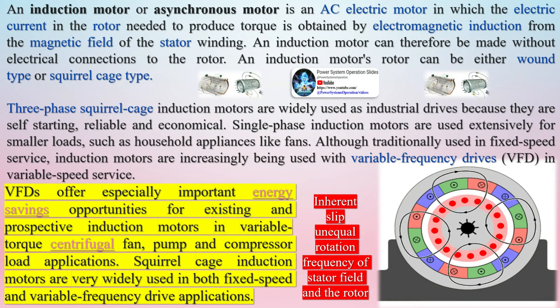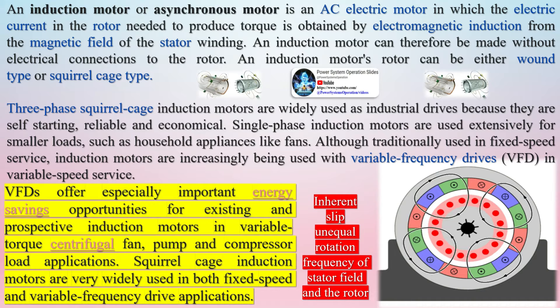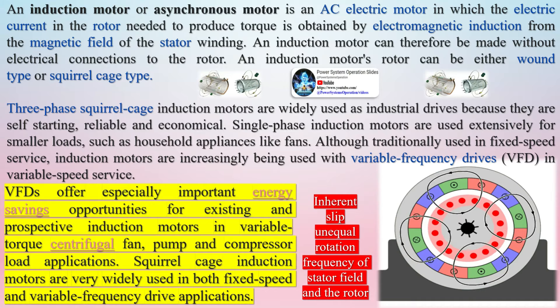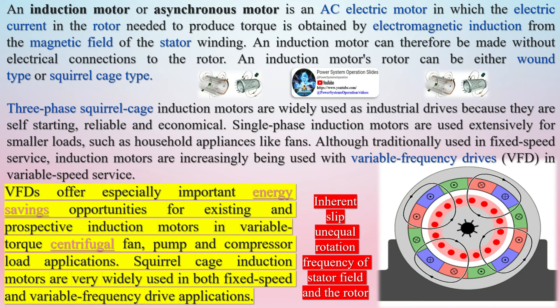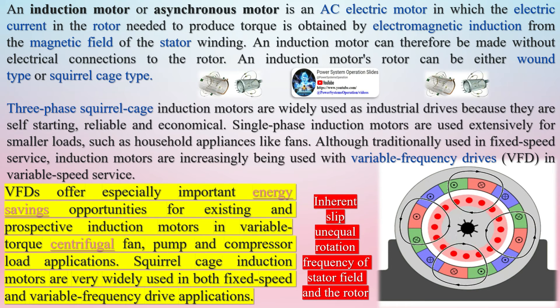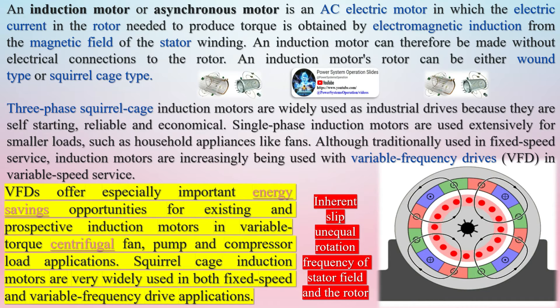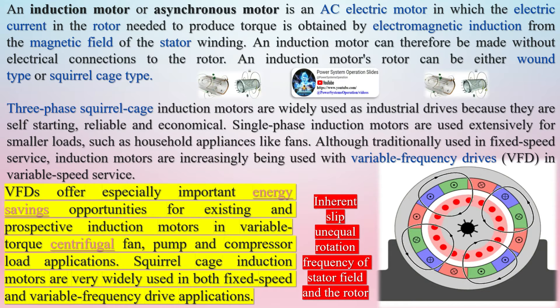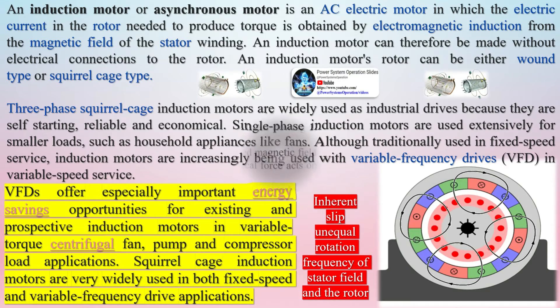Single-phase induction motors are used extensively for smaller loads, such as household appliances like fans. Although traditionally used in fixed speed service, induction motors are increasingly being used with variable frequency drives (VFD) in variable speed service. VFDs offer especially important energy savings for existing and prospective induction motors in variable torque centrifugal fan, pump, and compressor load applications. Squirrel cage induction motors are very widely used in both fixed speed and variable frequency drive applications.